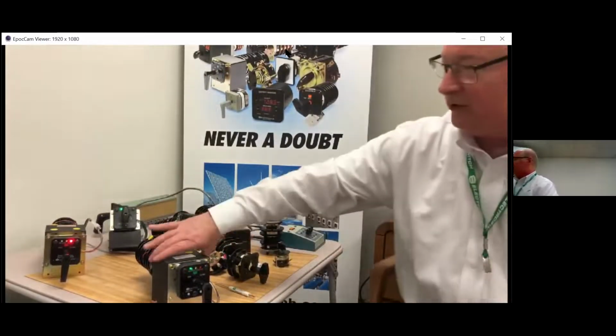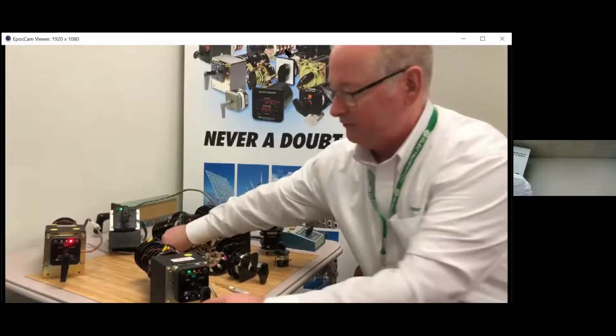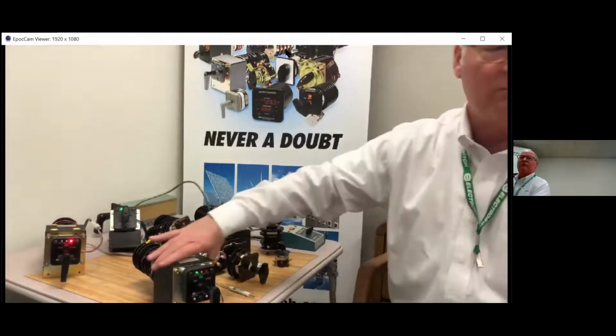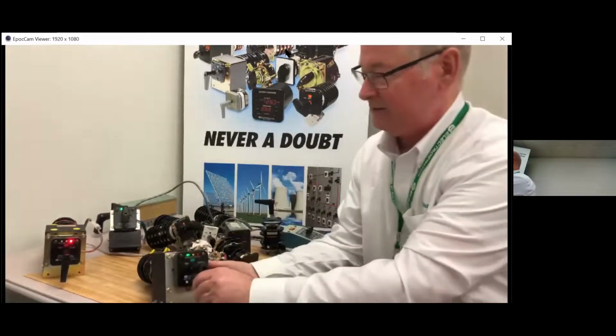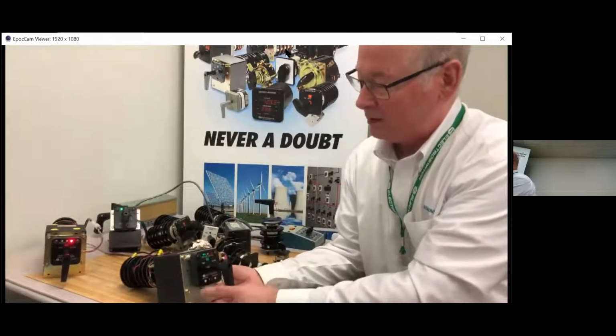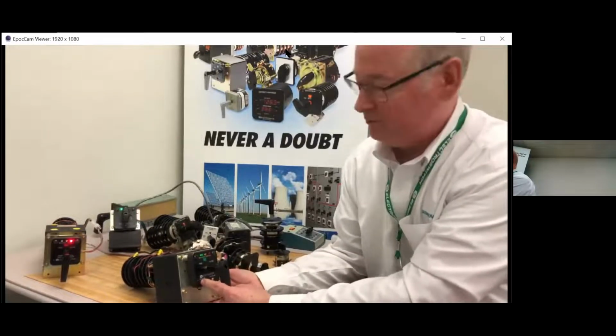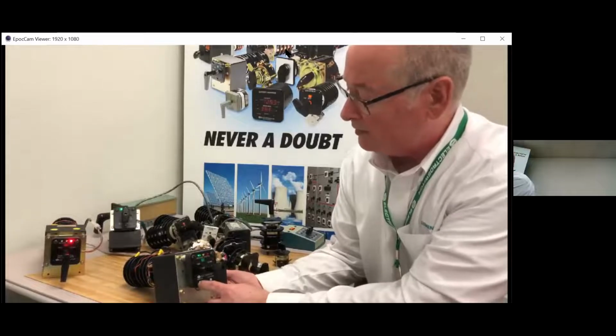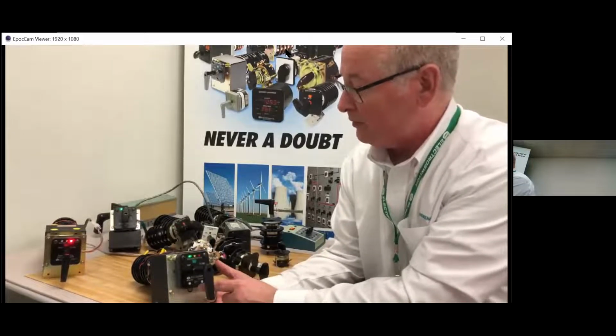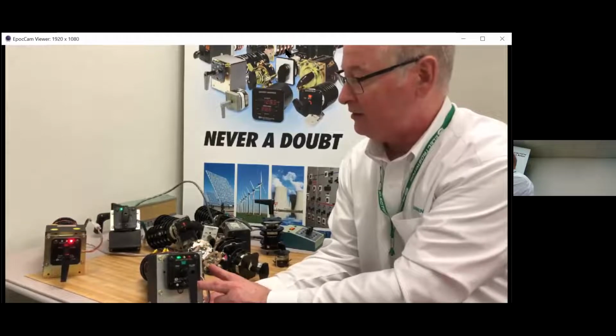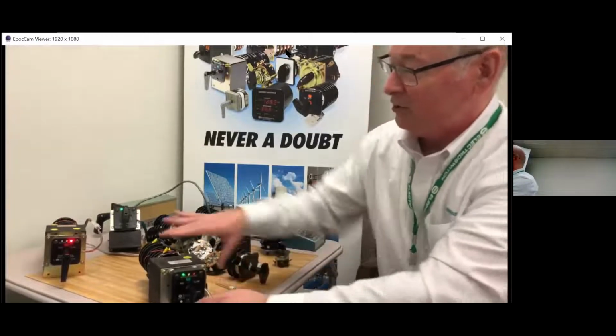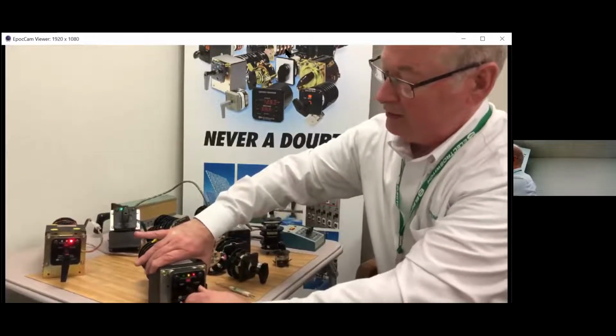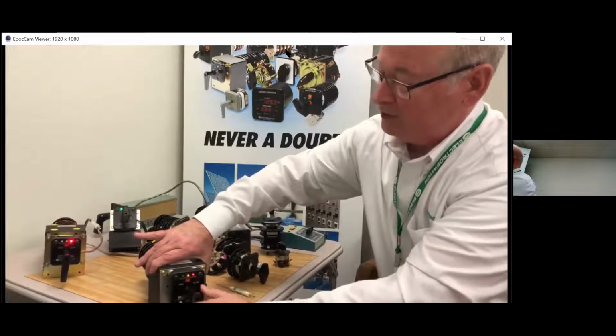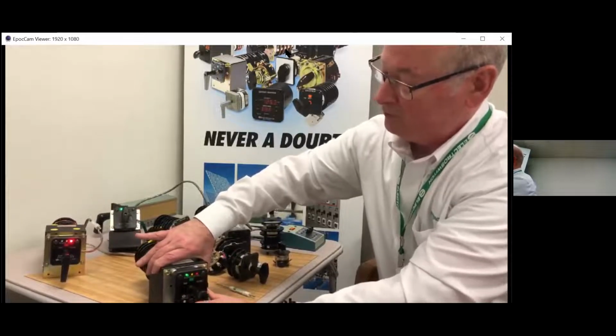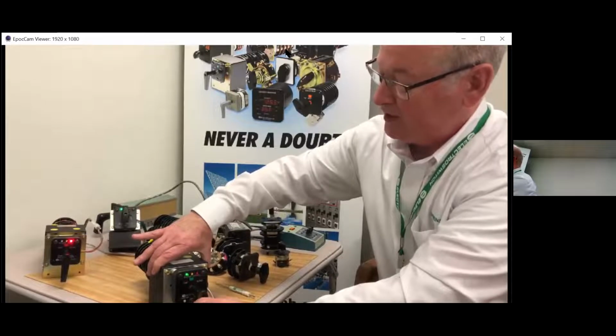Now this control switch looks very similar to the other control switch relay that I had up here before, but this one is a little bit more unique in that it has a couple of push buttons on either side of the lighted nameplate. One at the bottom here called delay open, and the other one on the other side called delay close. And so this is a manually operated function, as well as a remote operated function through SCADA.